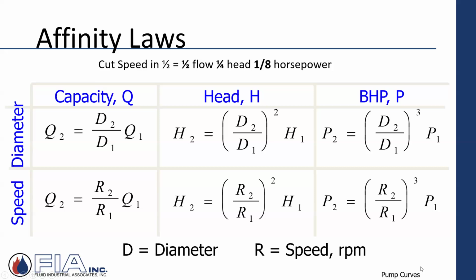But today, with variable speed drives, we're hardly ever doing that. We're just putting a drive on it, and we can ramp that drive down. And in changing the speed, it's the same as if you change the diameter of the impeller. You just change the RPMs. So in this case here, 1-to-1 on the flow rate, a squared relationship on the head as you change the speed, and a cubed relationship as you change the speed on the power consumption. So 1-to-1, squared, cubed. Very important.